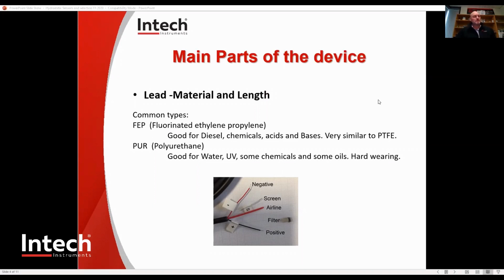In the lead, you'll find an airline. I'll show you, we can see in the image here an airline, the screen, which gives it some electrical protection from any other signals. You've got your positive lead, and you have your negative lead. The airline is very important because it needs to be able to breathe and allow for that pressure equalization from being down a hole and underwater to normal atmospheric pressure. Now, this little filter here you can see in the image is very important to stop water from getting down. Make sure the airline has a filter to allow it to breathe, but stops any condensation or water going down. This will ruin the transducer electronics down the sensitive end, which is in the medium.